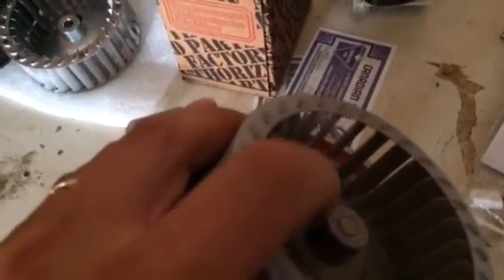The problem I have is with this set screw, because of the high temperatures inside the flue area, the set screw here has been baked on. I'm having a tough time getting it off. I'm going to try a little bit of penetrating oil on it.